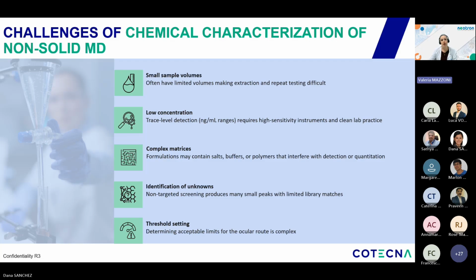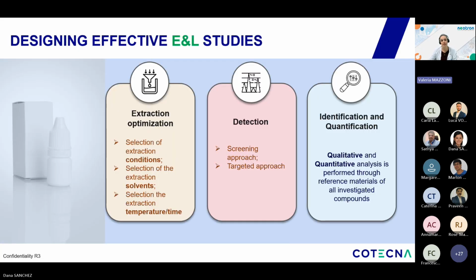But in general, how can we design effective extractables and leachables studies on these medical devices? Optimizing the studies begins with designing extraction conditions that are both scientifically justified and non-destructive, as I said before. We carefully select solvents, temperature, and contact times that challenge the material enough to reveal potential extractables, yet do not artificially degrade the device or alter the formulation. This balance is essential to generate meaningful worst-case data.